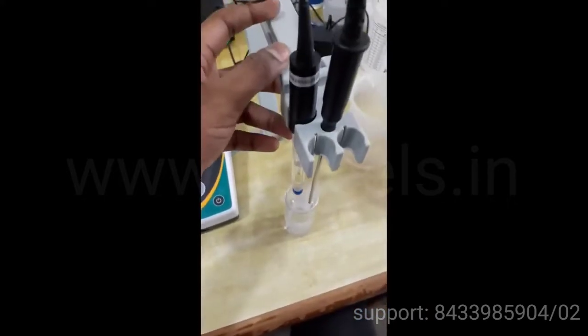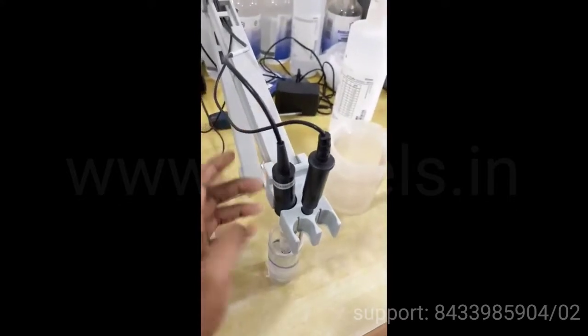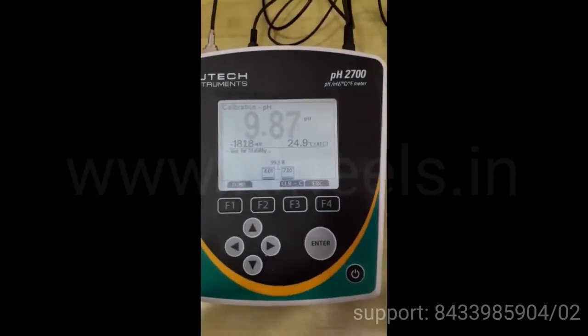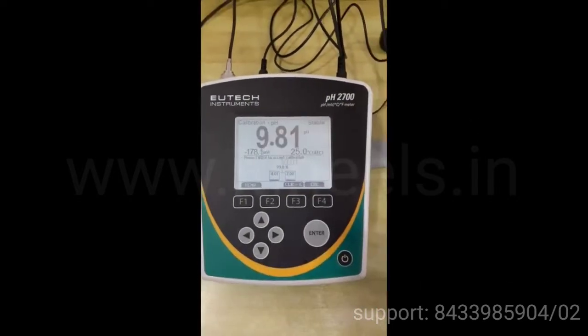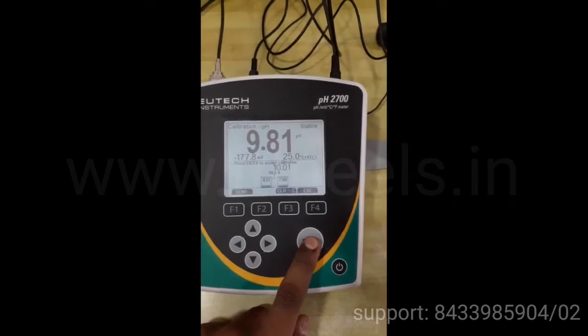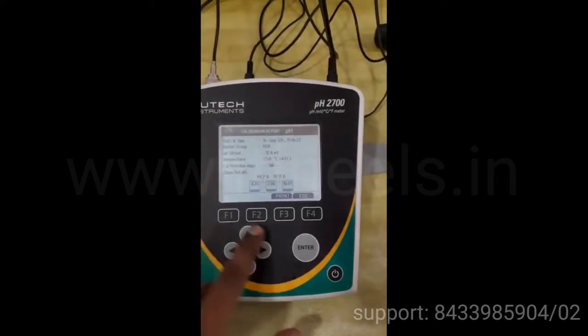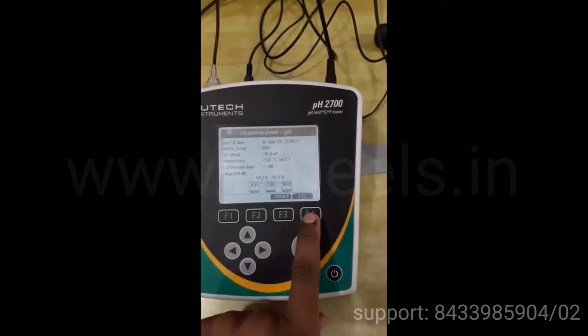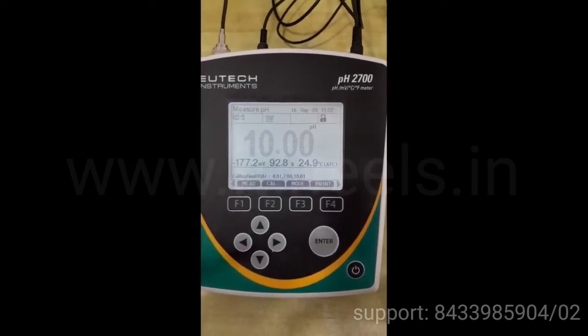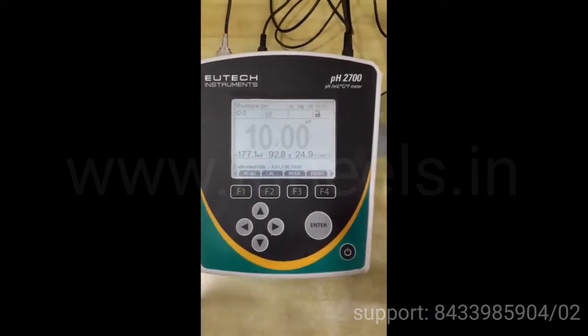Now we are going to calibrate it for 10 pH. So after cleaning, dip both ATC and electrode properly and wait for a stable indication. So we have set the meter for 3-point calibration. After accepting this reading, it will automatically return to measurement mode. After calibration, it displays the report. You can take a printout of this as well, or you can just escape. Now we have returned to measurement mode. It is also showing that we have calibrated it for 3 points.